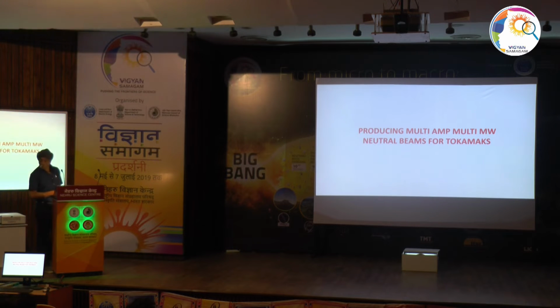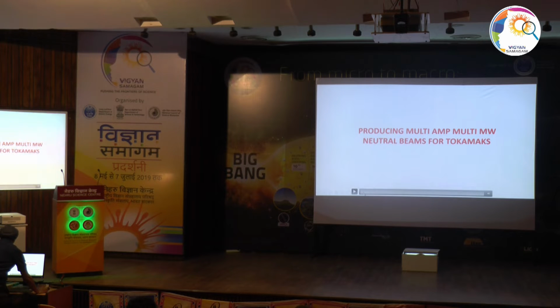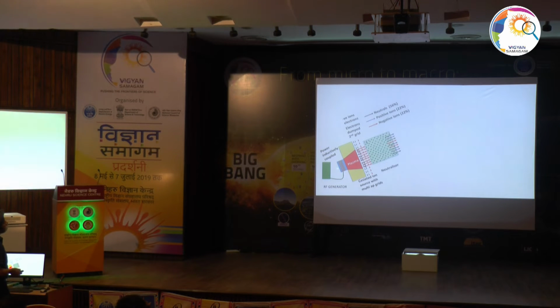So this was a small movie, just to illustrate what I said in a different way. We start with, as I said, an RF-based ion source. We have an RF generator. Inductively coupled power gives us a plasma. Then we go into a board which is called the surface board, where we inject cesium into the source, and we are able to get current densities of the order of 35 milliamps per centimeter square.